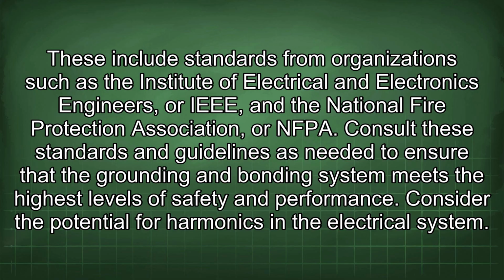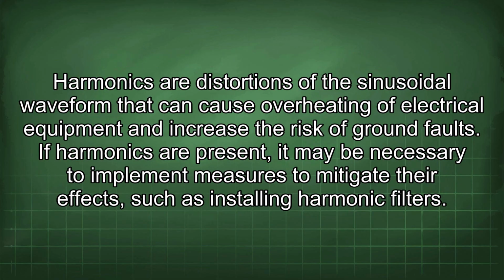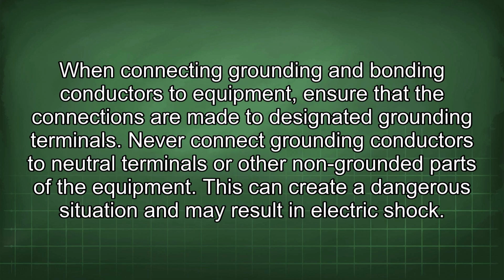Consider the potential for harmonics in the electrical system. Harmonics are distortions of the sinusoidal waveform that can cause overheating of electrical equipment and increase the risk of ground faults. If harmonics are present, it may be necessary to implement measures to mitigate their effects, such as installing harmonic filters. When connecting grounding and bonding conductors to equipment, ensure that the connections are made to designated grounding terminals. Never connect grounding conductors to neutral terminals or other non-grounded parts of the equipment. This can create a dangerous situation and may result in electric shock.